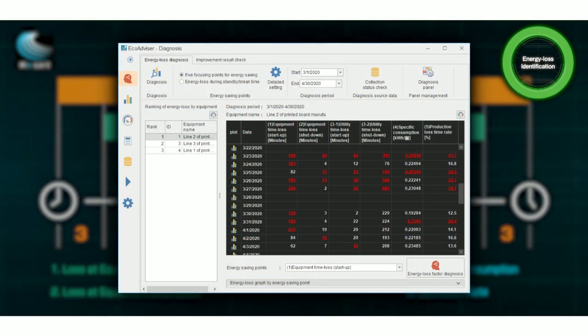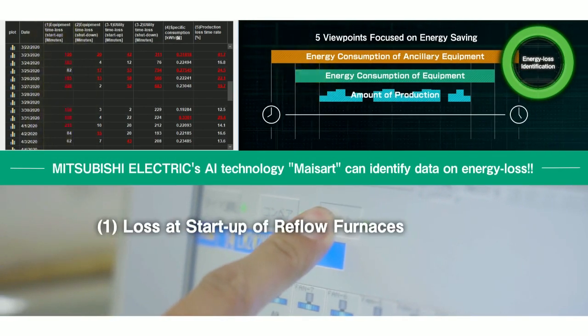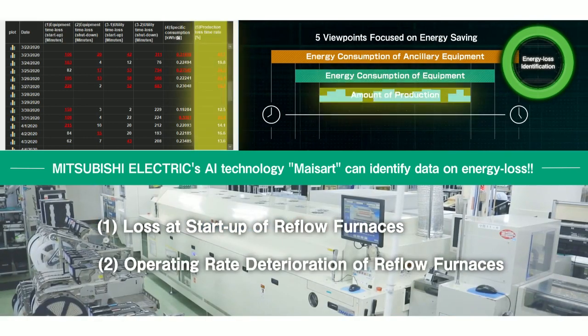Based on these five viewpoints, Maisart can identify data on energy loss. Results of its performance show there are two focusing points: loss at start-up of reflow furnaces, which resulted in a lot of wasted time, and operating rate deterioration of reflow furnaces, which was worse than expected.